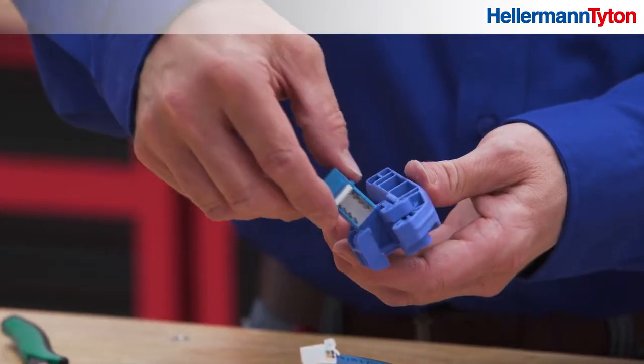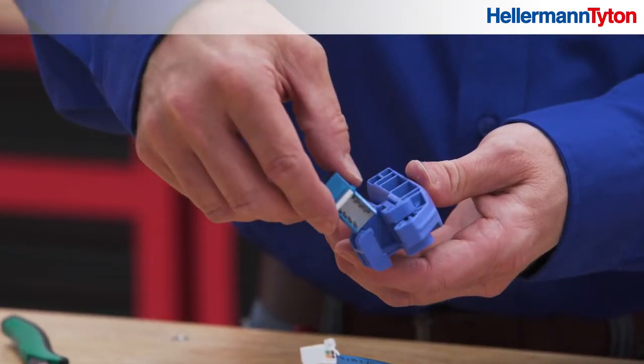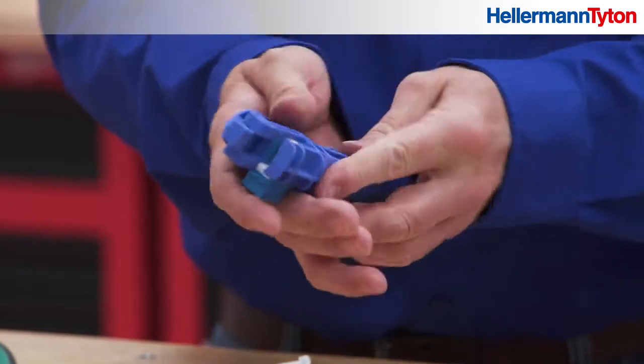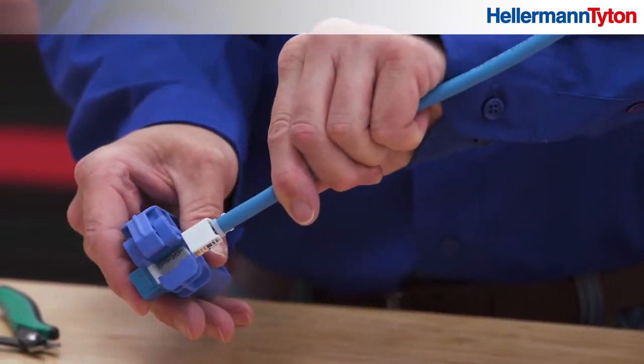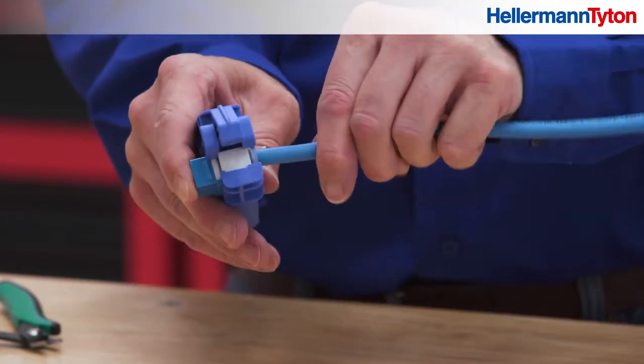Insert the jack body into the tool with the release clip facing down. Press it in until you hear it click. Push the manifold into the tool, wire side down. It will slide into place when it's aligned correctly.